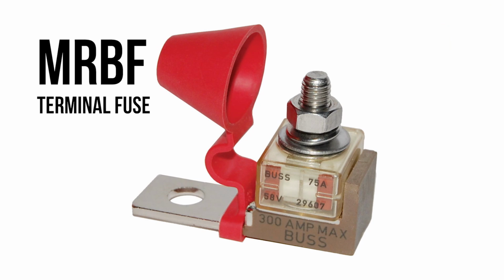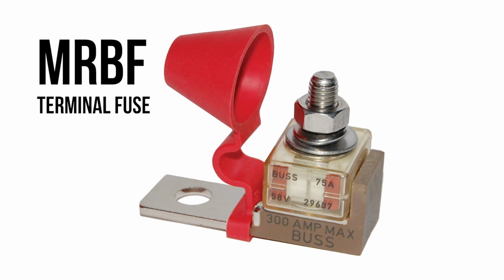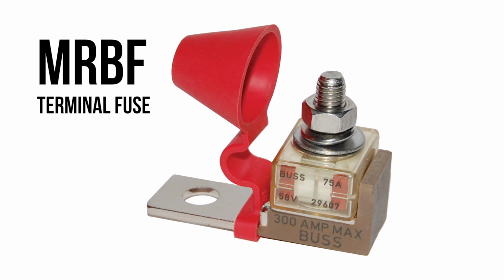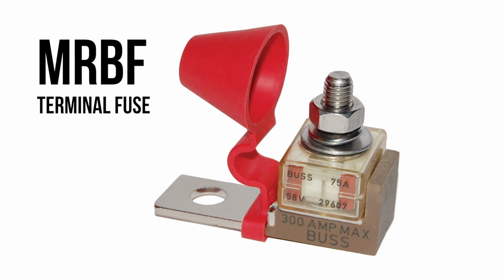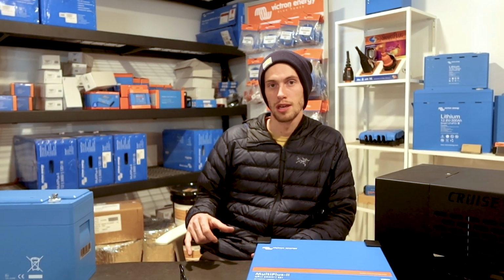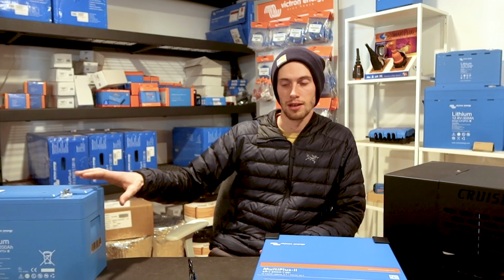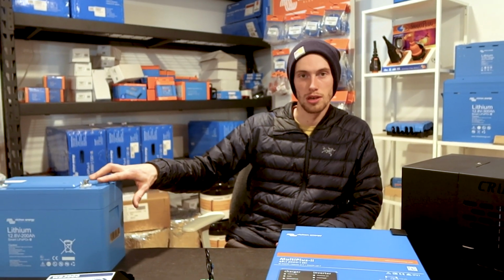So we like to use MRBF post fuses directly on our batteries before going into distribution. This also solves the issue of wanting your overcurrent protection as close to the source of energy as possible—putting a marine rated battery fuse on the terminal gets it as close to that battery as possible.